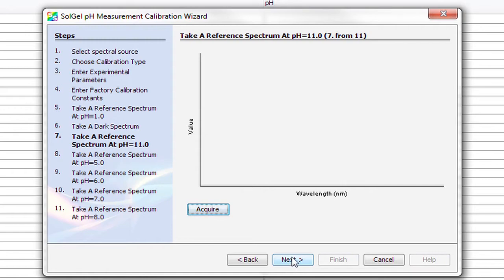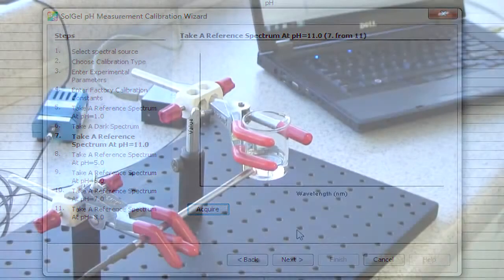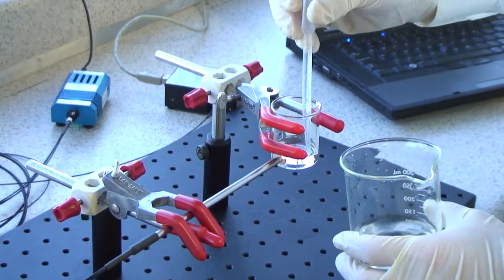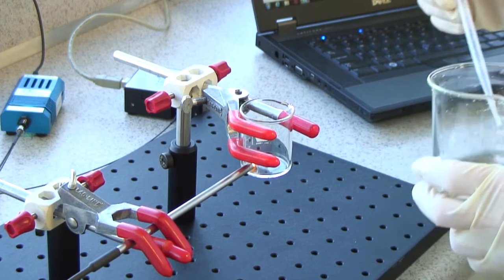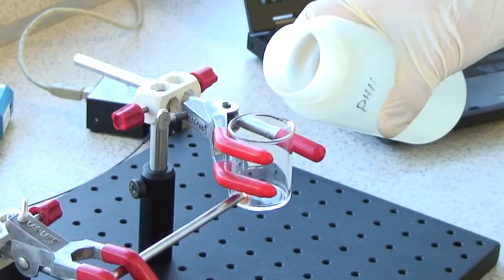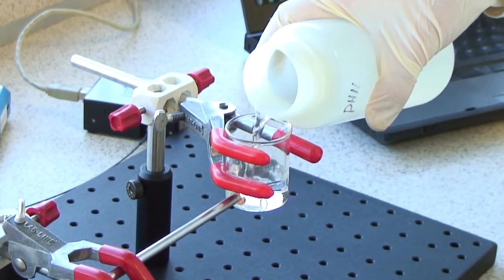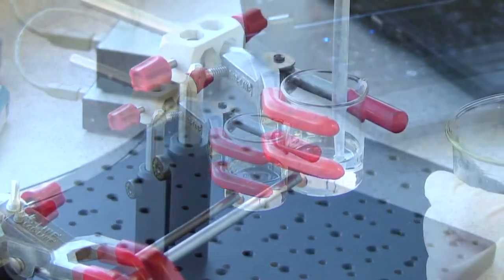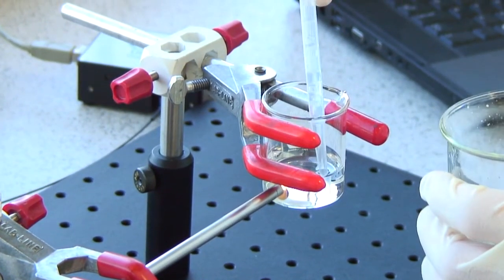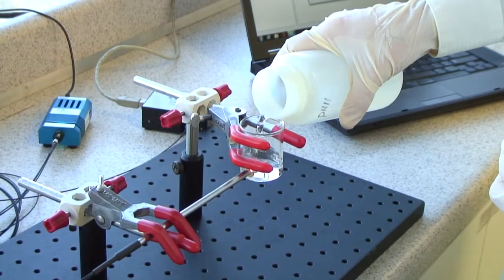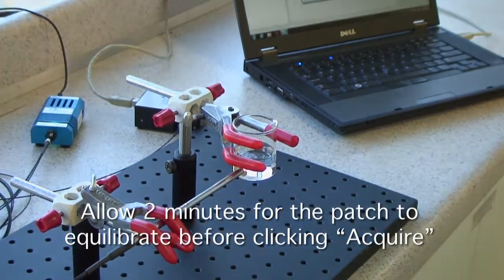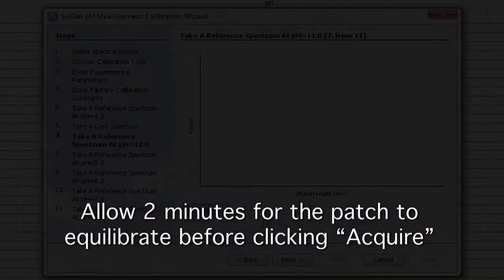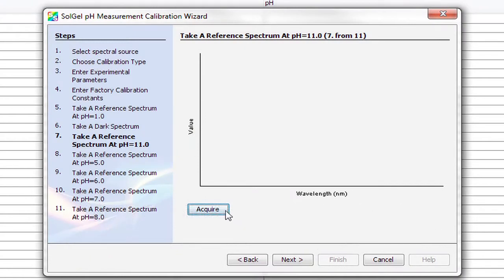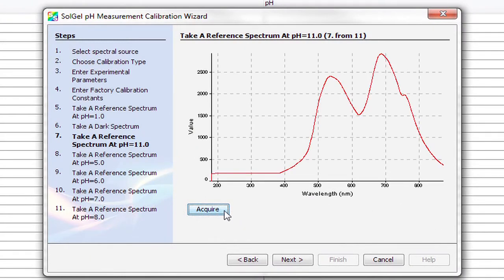Next, we'll want to expose the sensor patch to pH 11 buffer, though we don't want to disturb the setup. To do this, use a pipette to remove all of the pH 1 buffer and replace with pH 11. Wait 10 seconds, and then remove the pH 11 buffer in the same manner and replace with fresh buffer. Allow the patch 2 minutes to equilibrate before clicking Acquire. Once this has been acquired, click Next.